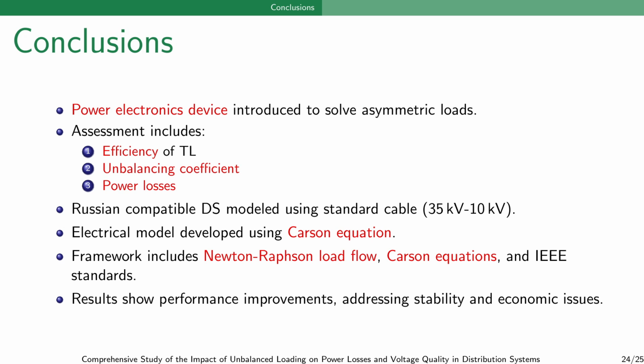In conclusion, we introduce a power electronic device to address asymmetrical load. Our assessment included the efficiency of the transmission line, the balancing coefficient, and power losses. We modeled a Russian-compatible distribution system using a standard cable and developed an electrical model using the Carson equation. Our framework incorporated Newton-Raphson load flow equations with the Carson equation and IEEE standards. The results show significant performance enhancement, addressing both stability and economic issues.